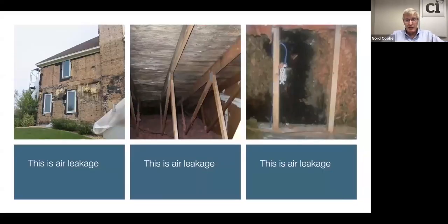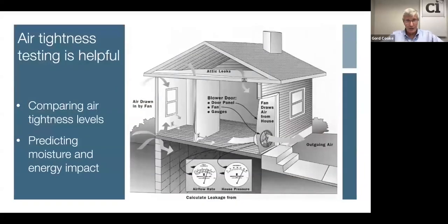And understanding that the pictures we're showing here are the result of air leakage. Sometimes we hear folks saying, no, it's because the house was too tight. No, it's because the house wasn't tight enough. Warm, moist air leaking into cold cavities, condensing on the inside of that cavity with no way to escape. That's all air leakage. That's why it's in the code.